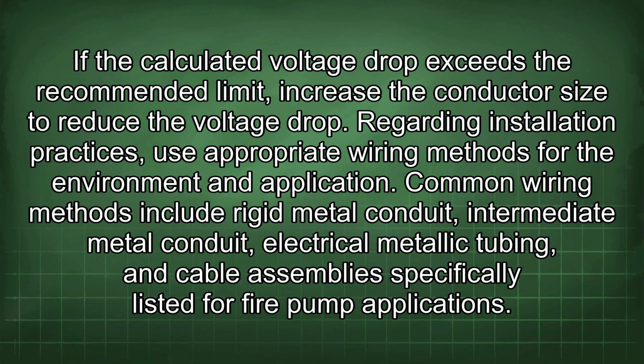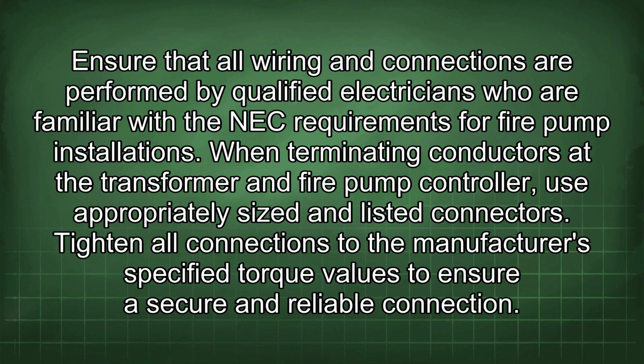Common wiring methods include rigid metal conduit, intermediate metal conduit, electrical metallic tubing, and cable assemblies specifically listed for fire pump applications. Ensure that all wiring and connections are performed by qualified electricians who are familiar with the NEC requirements for fire pump installations. When terminating conductors at the transformer and fire pump controller, use appropriately sized and listed connectors. Tighten all connections to the manufacturer's specified torque values to ensure a secure and reliable connection.